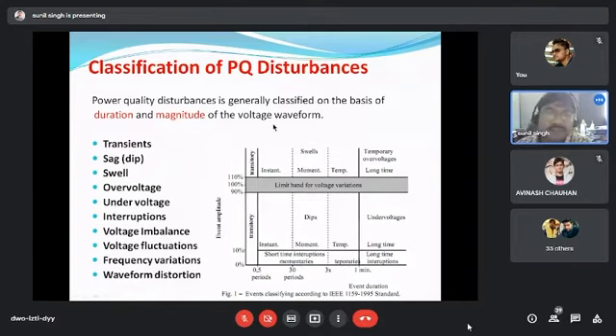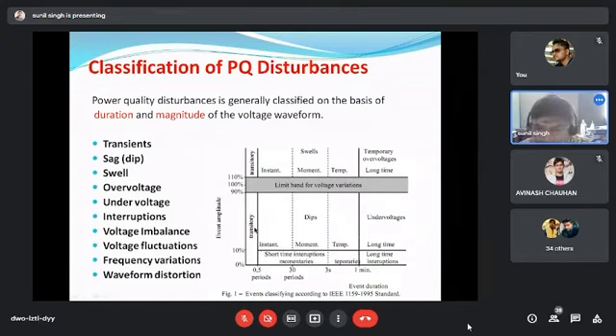Three categories may be there. This is how they define the power quality disturbances. Duration and magnitude will decide, or can be used to classify, the power quality disturbances. How to classify? Duration from 0 to 0.5 cycle is known as the very short duration, instantaneous. 0.5 cycle to 1 minute is the short duration power quality disturbance. And if any power quality disturbance remains for more than 1 minute, it is known as a long duration power quality disturbance.